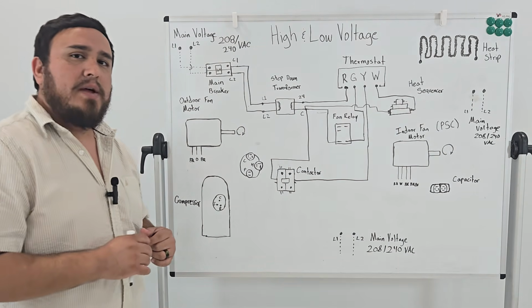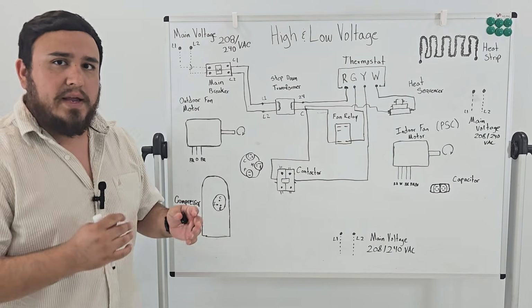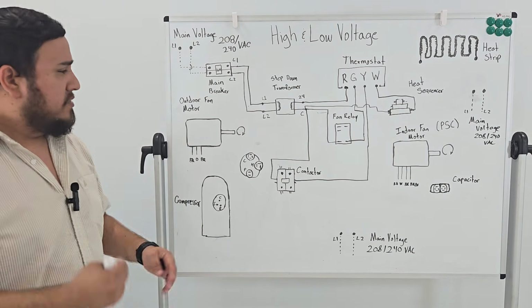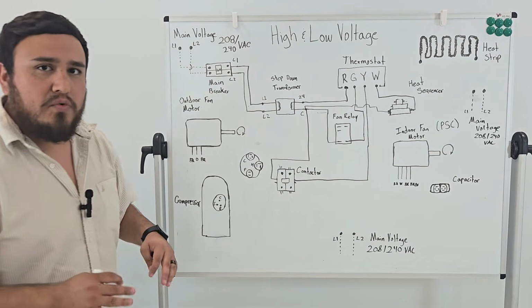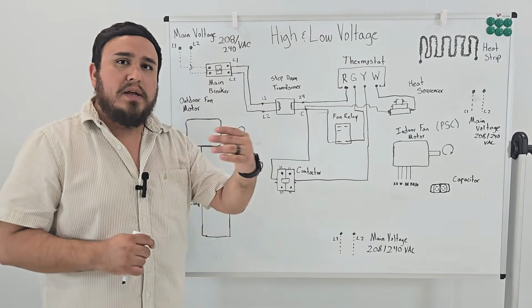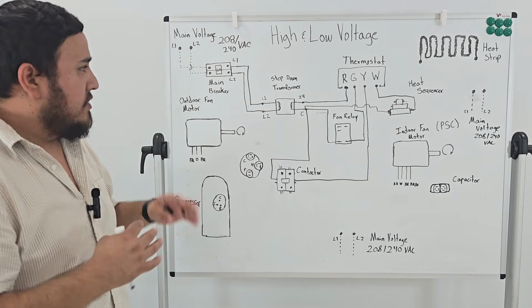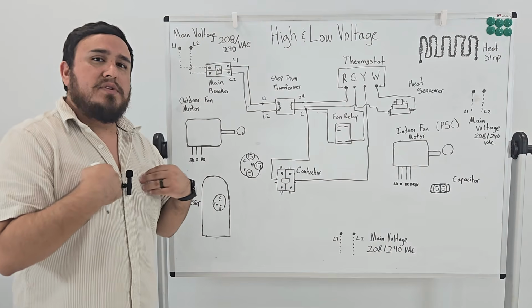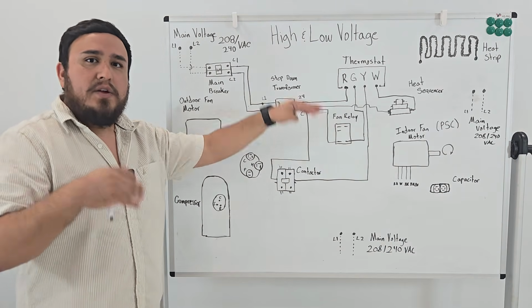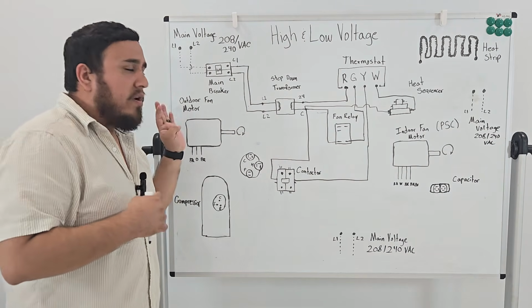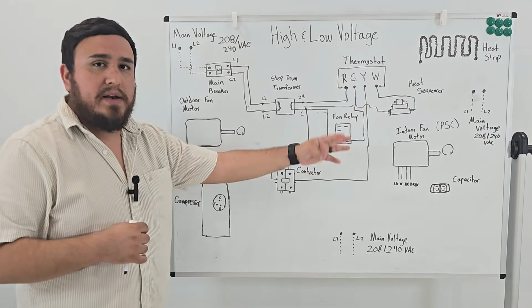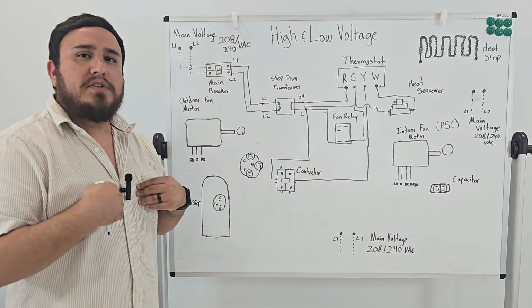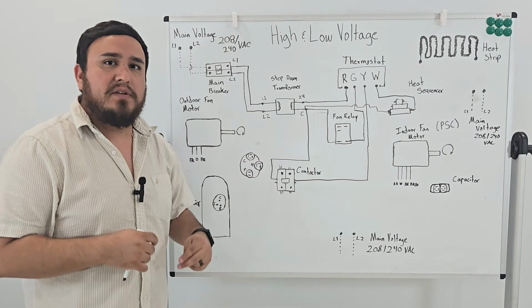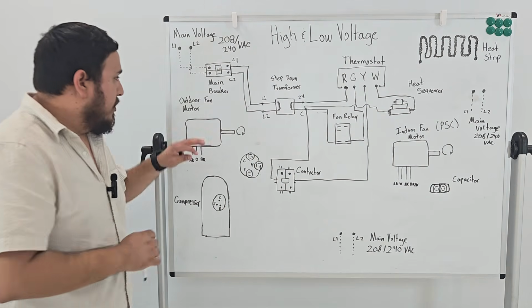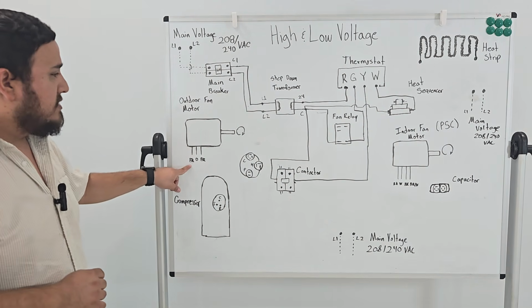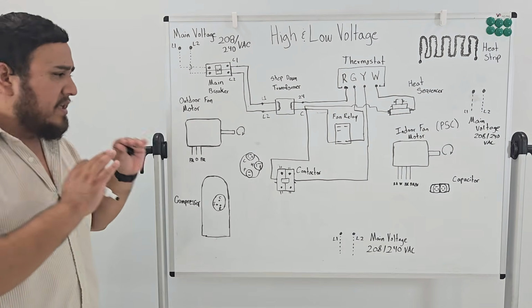Now, normally your outdoor fan motors come with 3 wires. OEMs, the ones I've seen the most, come with a black, orange, and brown wire. Sometimes you'll have a yellow, purple, and a brown wire as well. All right, so we have to understand how to wire things up. It doesn't matter if all the wires are black, just like I'm doing right now. As long as I know where these wires go, my air conditioning system is going to work the way it needs to function. Now I go back to my indoor fan motor. Let's get started with my black wire. Well, let's go ahead and do this.